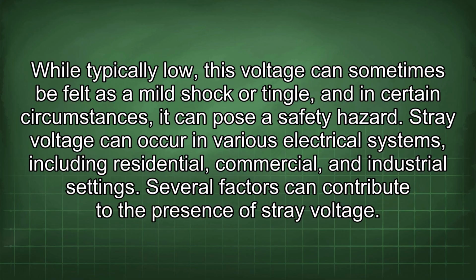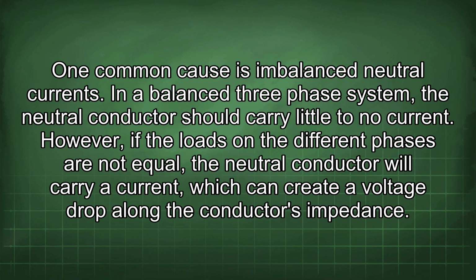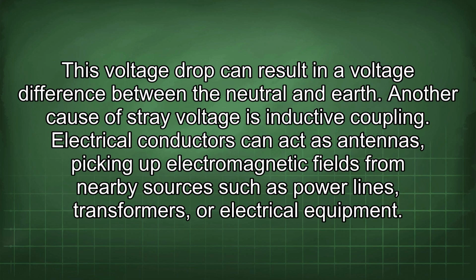Several factors can contribute to the presence of stray voltage. One common cause is imbalanced neutral currents. In a balanced three-phase system, the neutral conductor should carry little to no current. However, if the loads on the different phases are not equal, the neutral conductor will carry a current which can create a voltage drop along the conductor's impedance. This voltage drop can result in a voltage difference between the neutral and earth.